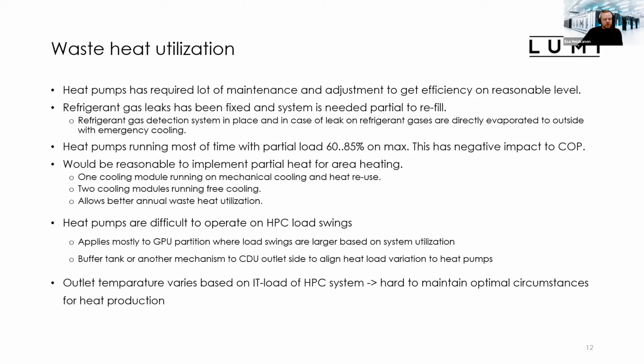And as I saw, the heat pumps are difficult to operate on these large HPC load swings, which applies mostly to the GPU partitions. And the outlet varies a little bit based on the IT load of the HPC system, so it's hard to maintain optimal circumstances for the heat production.